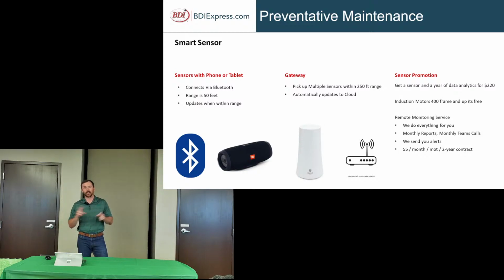But these Internet of Things, we've been doing a lot at hospitals, large campuses, but there's technology out there that you can monitor your equipment via Bluetooth, via your computer, using a gateway. What these devices do is they will monitor temperature and vibration. If you're looking at air handling unit 1, there's a chart that you'll look at. It'll show 2 waves of heat and vibration. If your heat just starts spiking, something could be wrong with that. If you see your vibration spiking, a bearing could be failing. If you see it just completely fall off, your unit might be turned off, or something might have come disconnected.